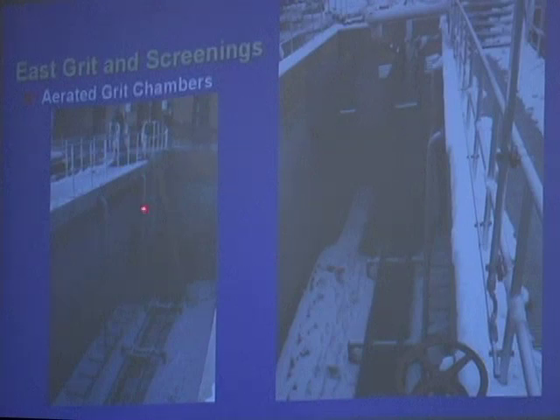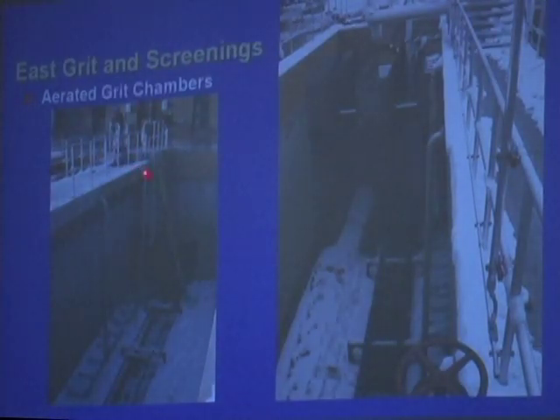A fill line valve right here, located at the base of the channel. This is the head end of the chamber. The sluice gate that allows the water to enter the chamber is located right here, with its operator directly above. The controls, the disconnect for that and the controls for that are located locally in the field here.